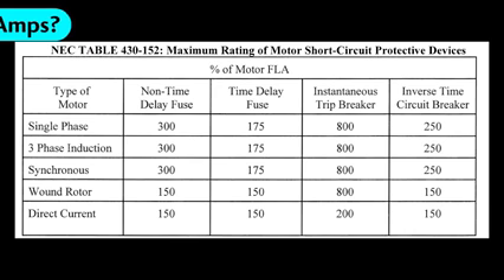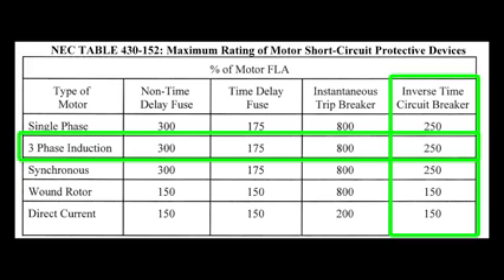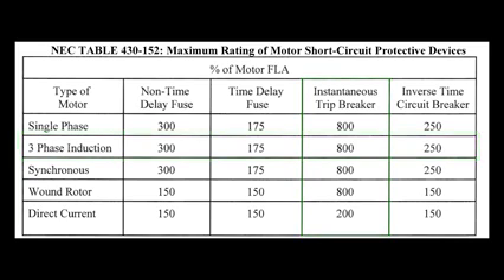Sizing a circuit breaker for use with a motor is easy. In the US, you just go to Table 430-152 of the National Electric Code and look up the answer. For motors, you want to use this inverse time breaker column, which says size the breaker at 250% of the motor's full load amperage. This instantaneous column is for high inrush loads. You wouldn't want to use that with a motor. It would allow the motor to run at 800% of capacity indefinitely. If you're using a fuse on a motor, you would want to use this column for the same reason.